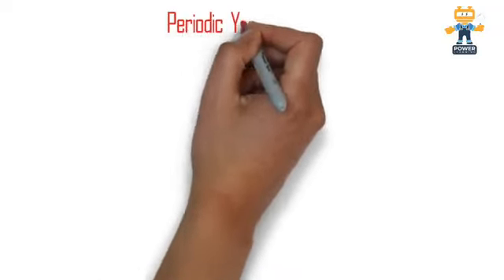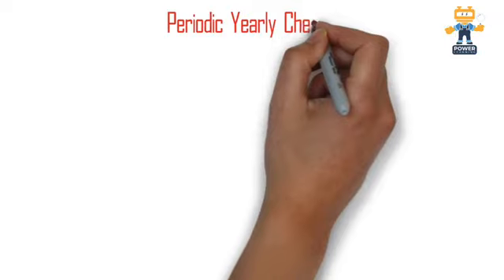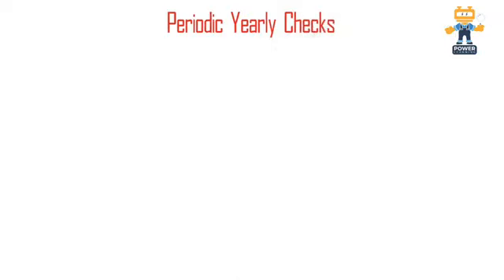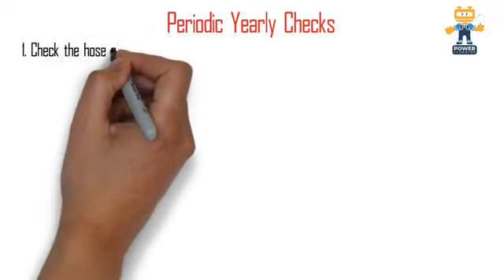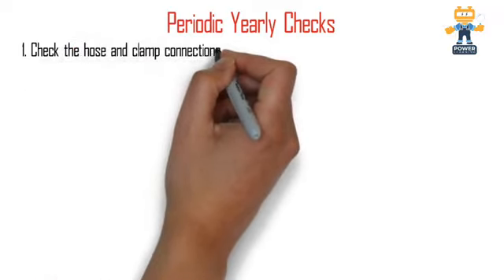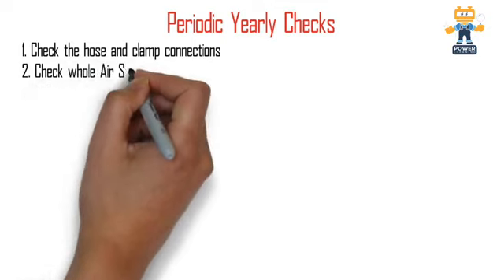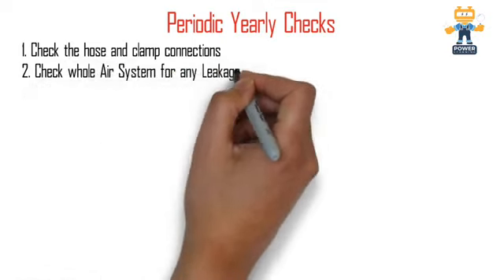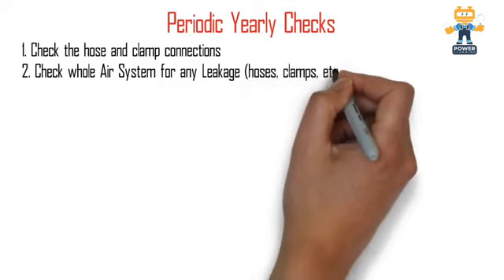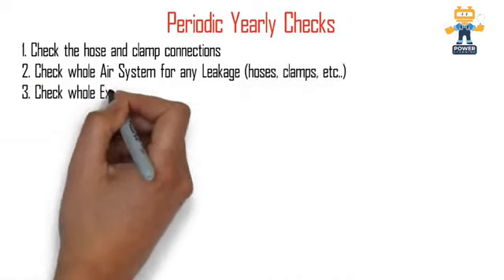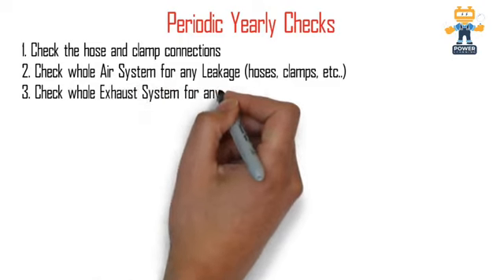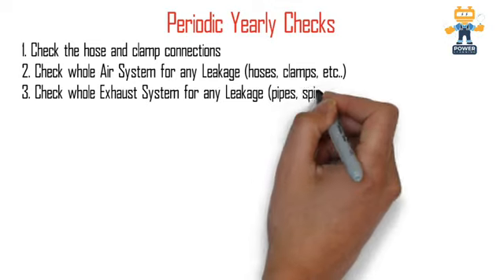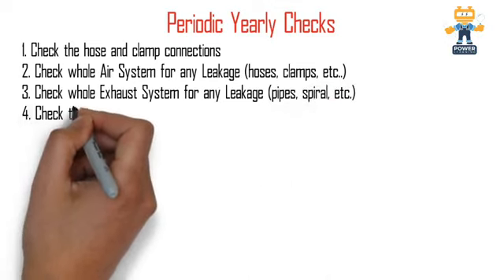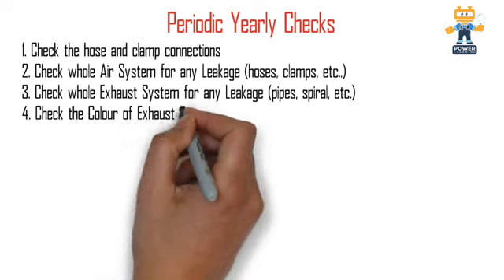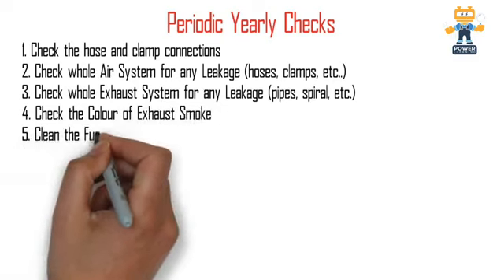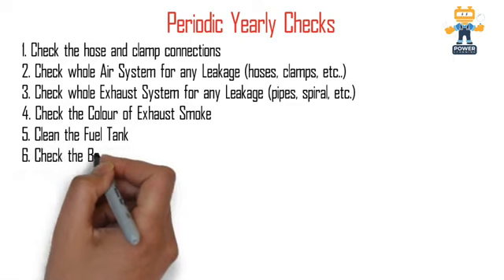After that we have the periodic yearly maintenance. Normally this is done for standby sites, but you have to do it for your prime generator also. Every year you have to check all these things in order to maintain your generator in good condition. Check the hose and clamp connections. These are very important. Check the whole air system for any leakages, like hoses and clamps. If they are loose, you have to tighten them. Be careful about the air system: if it is loose, the generator has less efficiency. Similarly, check the whole exhaust system for any leakages, as it will also affect generator efficiency.